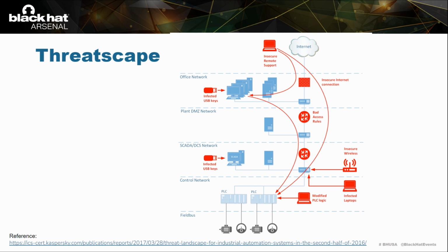SCADA stands for Supervisory Control and Data Acquisition. Now, these systems have a high-level overview of the machines that are being controlled, the PLC, the field bus, and show the data from the sensors, the PLCs, all of these things that interface with the plant machinery. Then comes the control network, where the actual programmable logic controllers, the PLCs, are present, which communicate with the field bus.